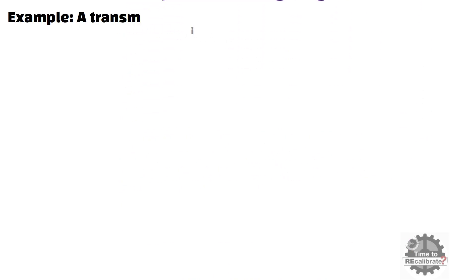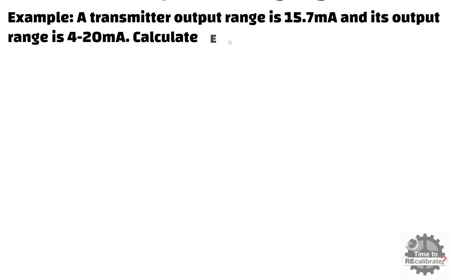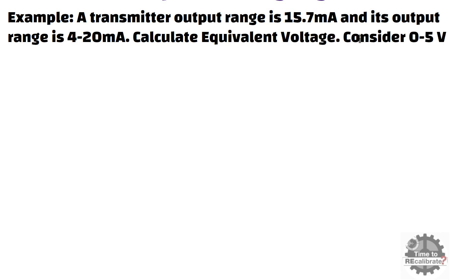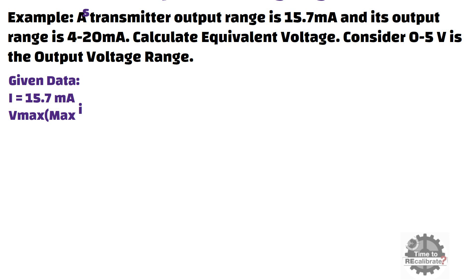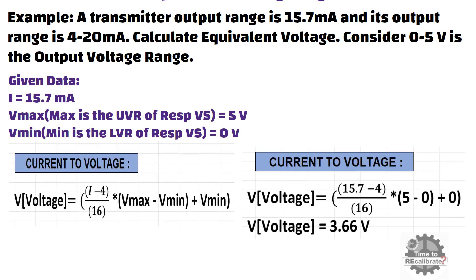For example, a transmitter output is 15.7 milliamperes and its output range is 4 to 20 milliamperes. Calculate the equivalent voltage, considering 0 to 5 volts as the output voltage range. The given data is: I = 15.7 milliamperes, Vmax = 5 volts, and Vmin = 0 volts. Putting all these values into the equation and doing the math, you will get 3.66 volts. In other words, when current is 15.7 milliamperes, the voltage value is 3.66 volts.